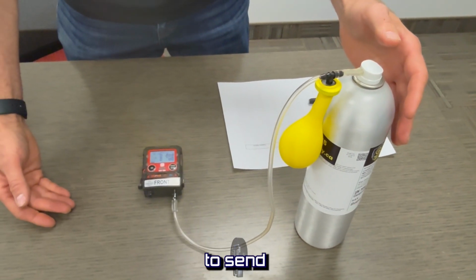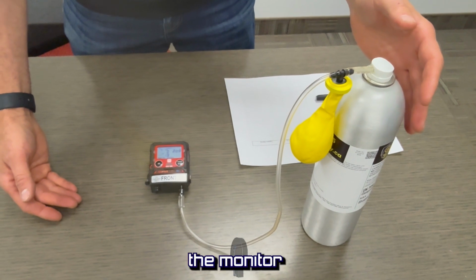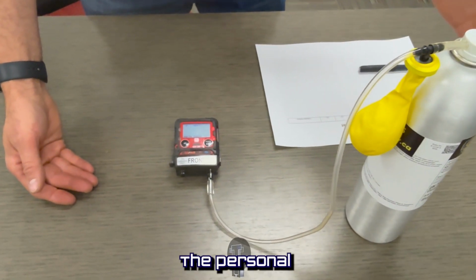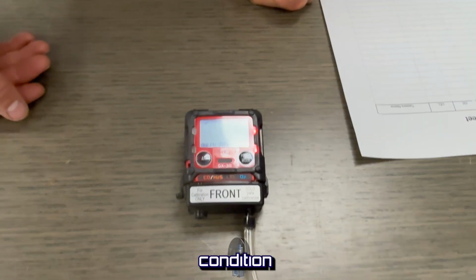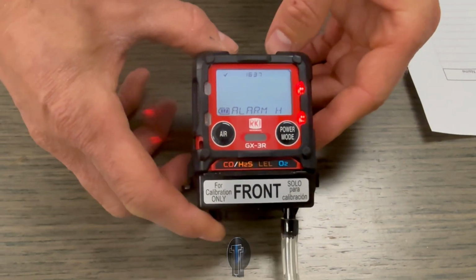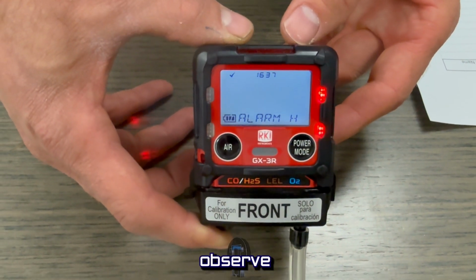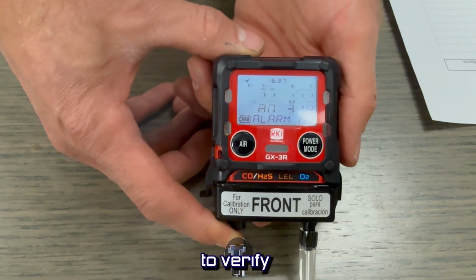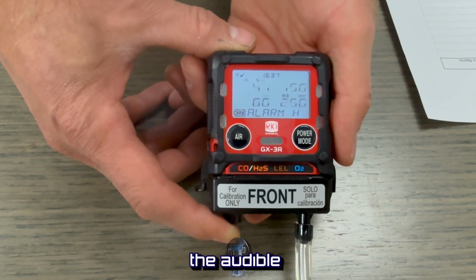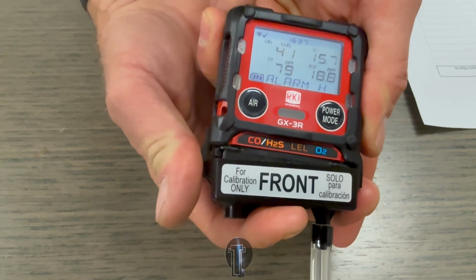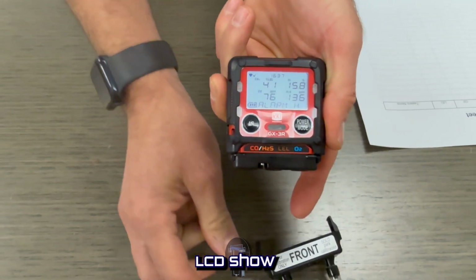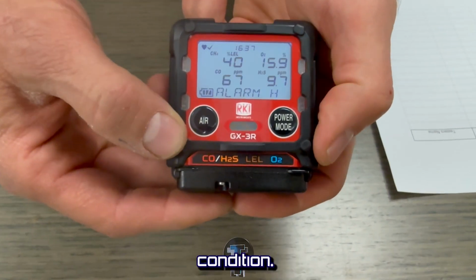Release the pinched tube to send the gas from the inflated balloon to the monitor sensors. The personal gas monitor should go into an alarm condition, indicating that the sensors and alarms are functioning properly. Observe the personal gas monitor to verify that the LEDs are flashing, the audible alarm sounds, the vibrating alarm is operational, and the LCD shows all the alarm readings of an alarm condition.